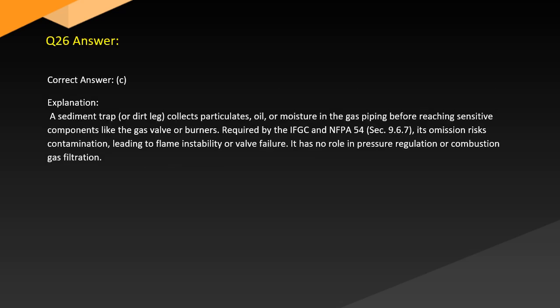Answer. Correct answer, C. Explanation. A sediment trap or dirt leg collects particulates, oil, or moisture in the gas piping before reaching sensitive components like the gas valve or burners, required by the IFGC and NFPA 54 Sec 9.6.7. Its omission risks contamination, leading to flame instability or valve failure. It has no role in pressure regulation or combustion gas filtration.